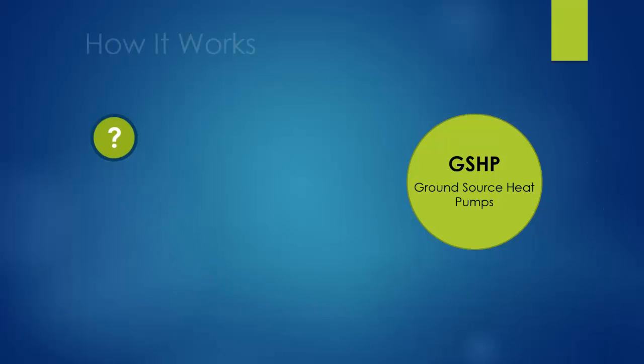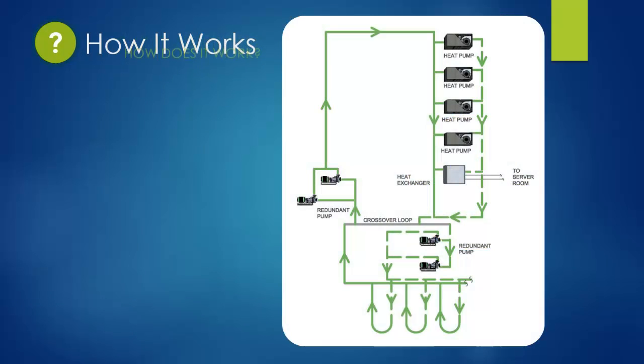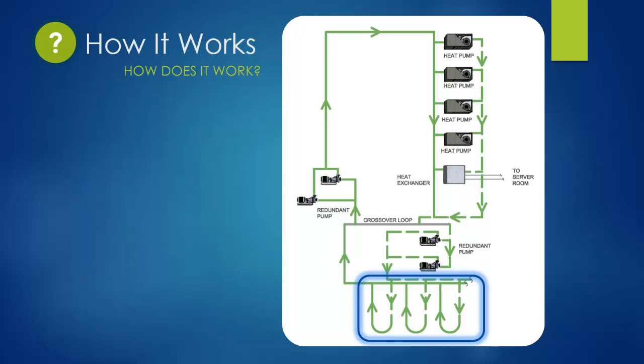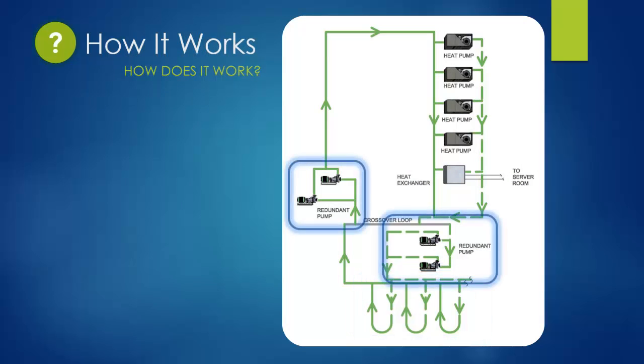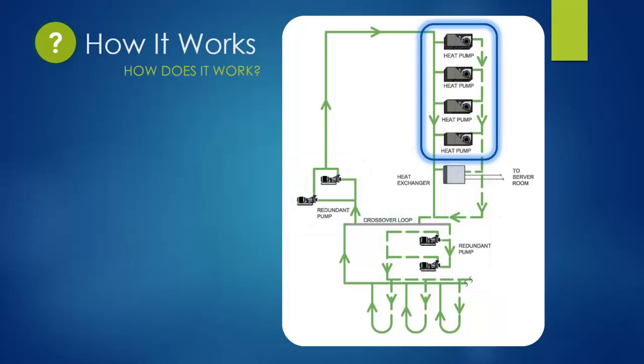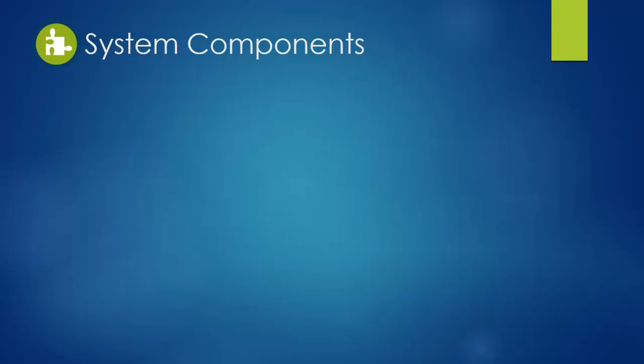Next, we will discuss how the system works. Ground source heat pumps work by pumping water through bores in the ground, which act as a heat source or a heat sink. To take the water to the terminal units, redundant pumps with a variable frequency drive are used. The water is then routed to water source heat pumps connected in parallel, which inherently allows load to be shared between the heat pumps. This section will begin by describing the ground source heat pump components that apply to the entire system. Then we will move into discussing components that apply specifically to an occupancy category.